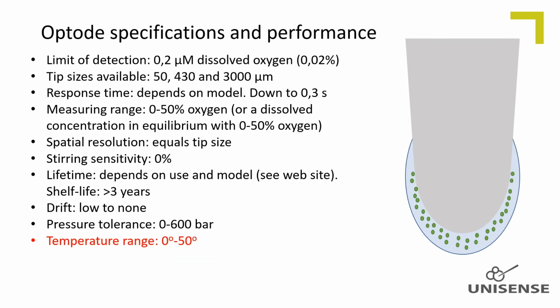I have already explained that the fluorescent dye bleaches fast at high temperatures. Therefore, we do not recommend using the Optode at temperatures higher than 50 degrees Celsius. At high temperatures, we recommend decreasing the frequency of measurements to increase lifetime.